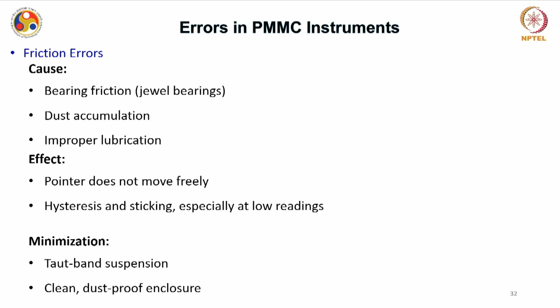manufacturing. Okay. Then another kind of error is the frictional error, and the cause is again the bearing friction because of the jewel bearings used. Okay. It can also be due to regular use, and in regular use there can be dust accumulation, or if you are not properly lubricating, these are mechanical parts. So, because of improper lubrication also this frictional error can occur.